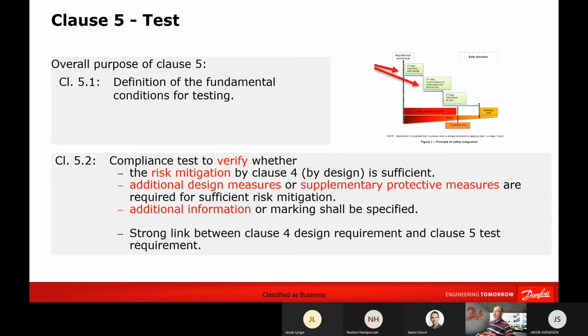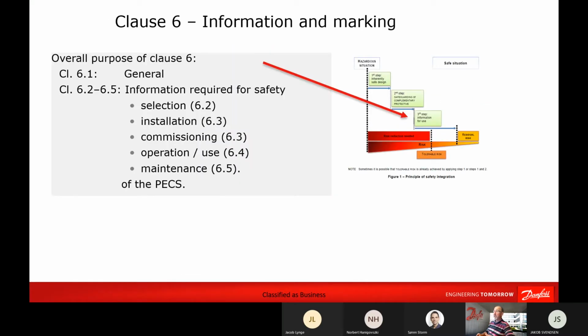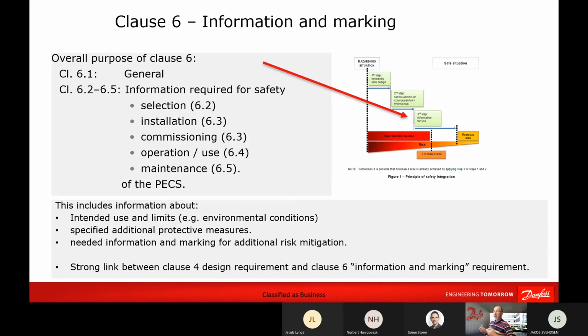Clause 5 is safety testing. It tells me if the design is sufficiently made, and also gives information about whether I need additional design measures or supplementary protective measures, and whether I need to inform my user by marking. Clause 6 is the marking, where I provide information to the user for selection of the product, for installation, commissioning, operational use, and maintenance of the PECS.